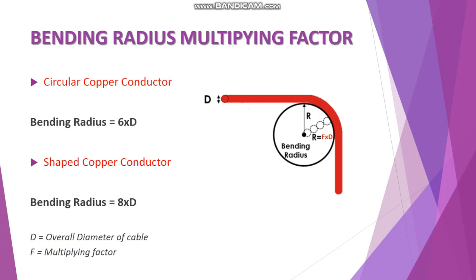When calculating bending radius, you need to first understand that there are two kinds of cable conductors available: one is a circular copper conductor, and the other is the shaped copper conductor. For a circular copper conductor, the bending radius is calculated with the formula R = F × D, where D is the overall diameter of the cable, and F is the multiplying factor. For circular copper conductor, F is 6; for shaped conductor, F is 8.